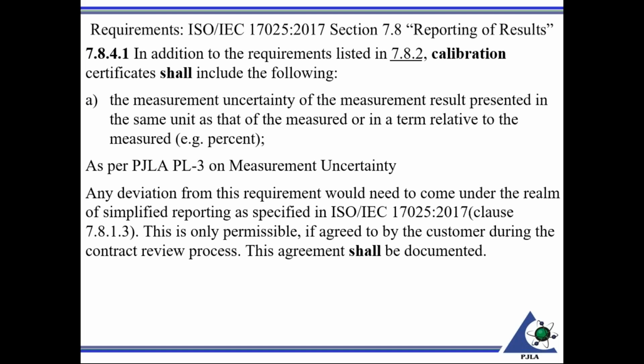So as per, and we're going to look at our policy PL3 on measurement uncertainty, a deviation from this protocol has got to be customer driven. It can't be shoved down the customer's throat: hey, we're not reporting uncertainty, we're not going to report it unless you tell us. Any deviation from this requirement would need to come under the realm of simplified reporting. So that is under section 7.8.1.3, which says you can report in a simplified manner. So anything that's under 7.8, which is reporting the results, for whatever reason, if the customer does not want one of these required elements in it, it could come under the realm of simplified reporting. The caveat, though, would be that you have to be able to go back and duplicate the required elements that were left off. And this would only be permissible if agreed to by the customer during the contract review.